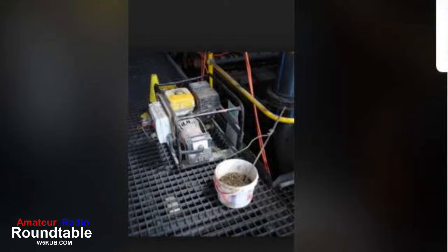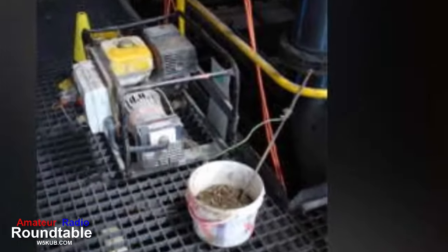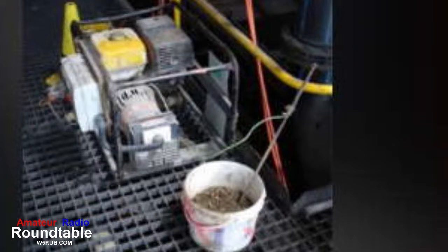Yes, and I don't know if Tom can find a picture of it, but what I have under my desk in my shack is a very large copper-plated metal grounding plate with lots of holes in it that I can use to bolt things to. I put my lightning protectors on there, and all of the wires that ground my radios go back to that. Then that has a very thick wire that goes out of the shack and down to the basement where it connects to the ground bus on the electrical panel, which is one of the places where you're allowed to ground things.